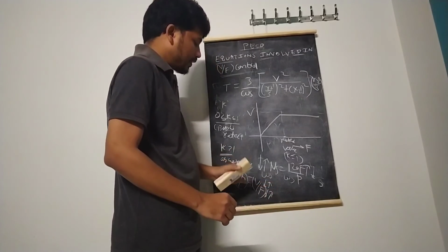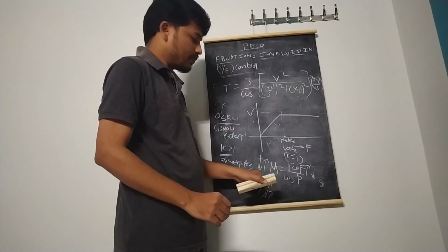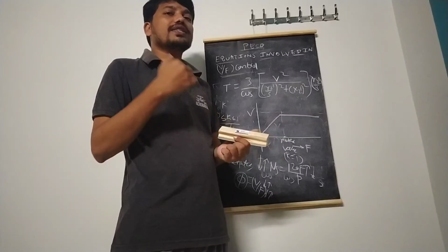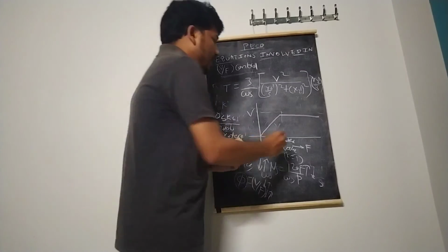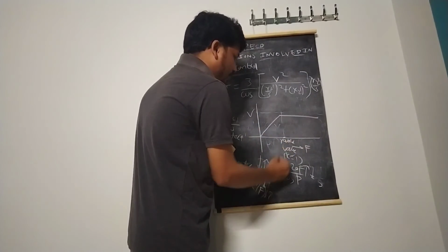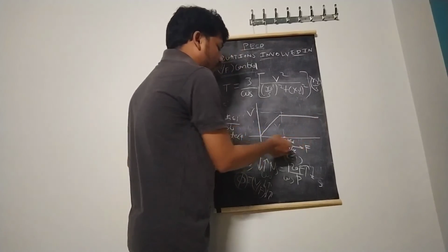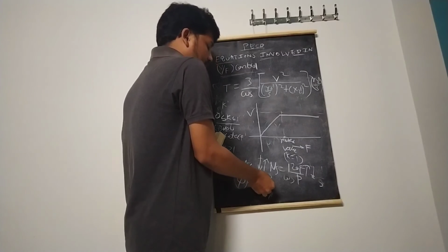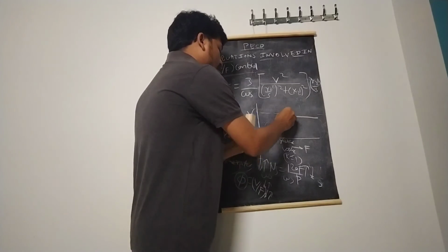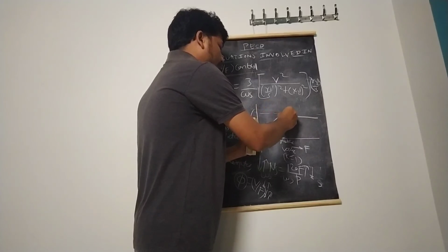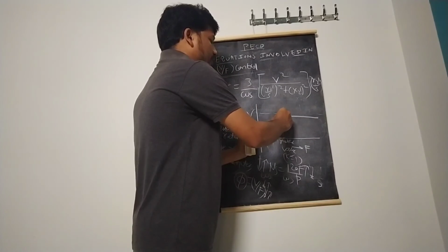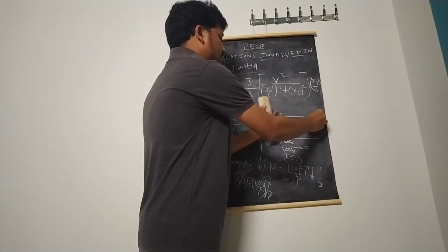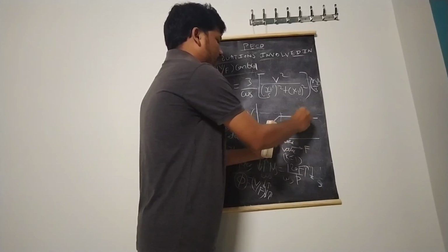That is the factor. But increasing the frequency is possible, while increasing the voltage beyond the rated is not possible in practical cases. Since nobody can give more than the rated voltage, that is why for above rated frequency, the voltage should be constant. For below rated, while decreasing the frequency, voltage decreases; as frequency increases, voltage increases up to this rated value, both are changed. The voltage can go 0 to 200, 300, 315, 380, 415 volts, but above 415 volts, it is constant. Above 50 Hz, the voltage is constant.